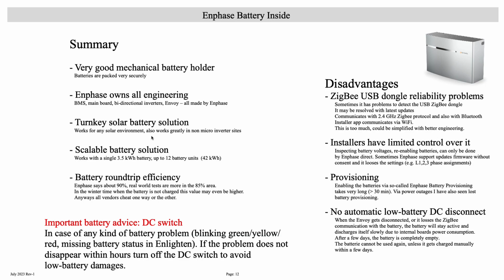That's very smart, I've done this for a couple of sites, and it works great. It's very scalable—I explained this earlier. You have a single battery unit with 3.5 kilowatt hours, and you can sum up to 12 of these units, maybe even more, but let's say the spec says 12. I don't know if using a second IQ relay lets us add more or tweak the software, but 12 is already 42 kilowatt hours. That's a lot.